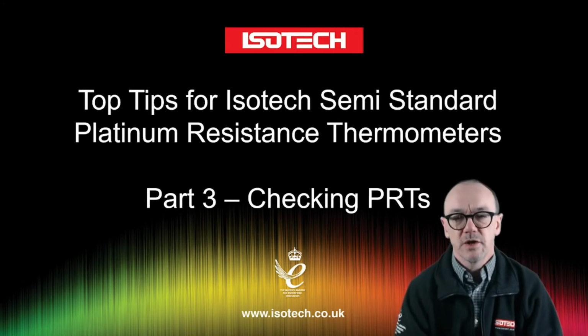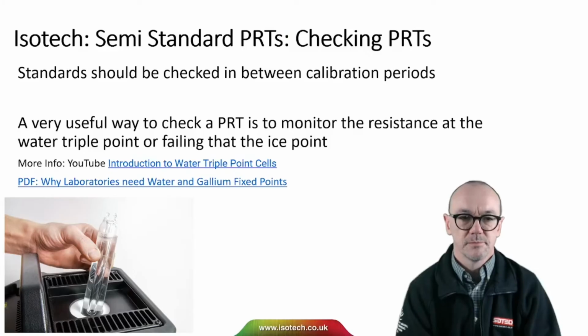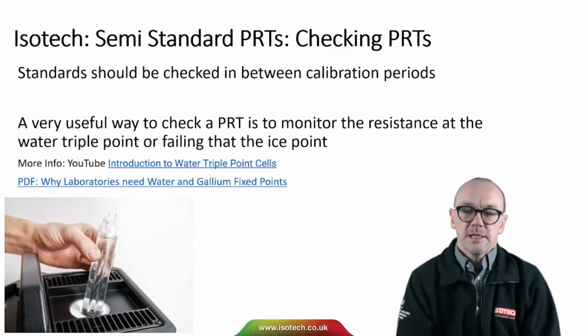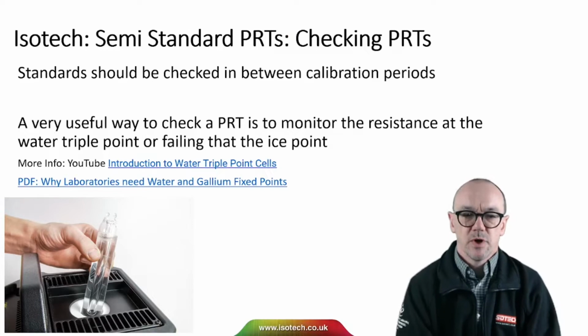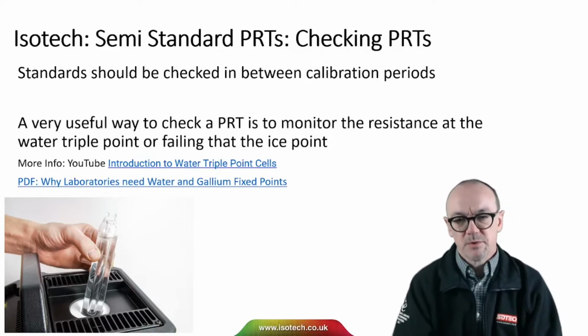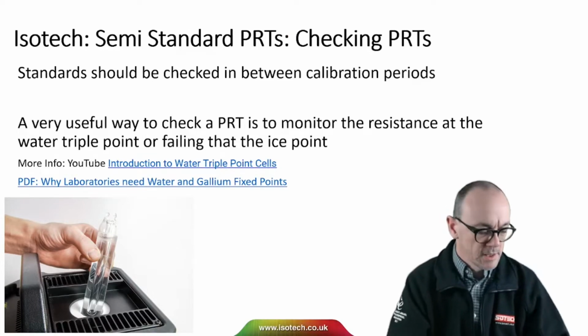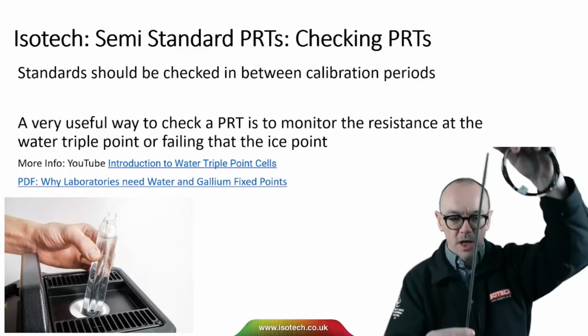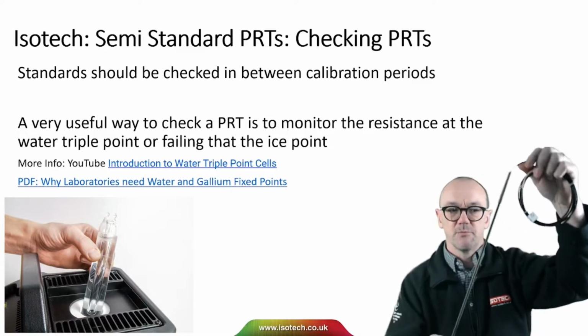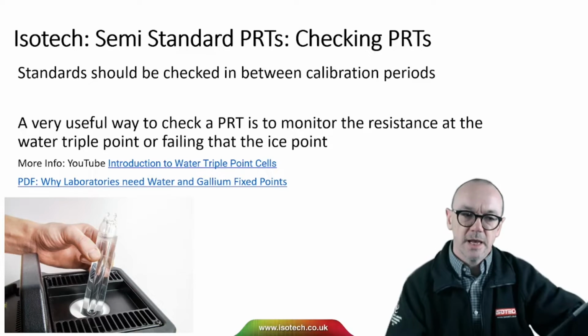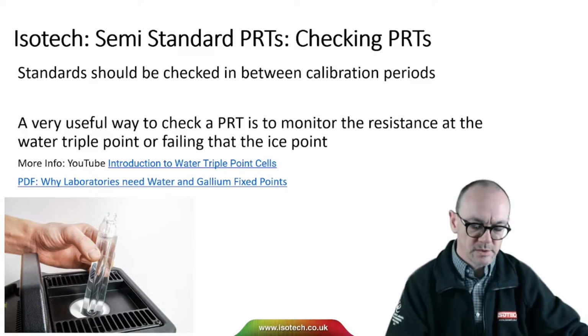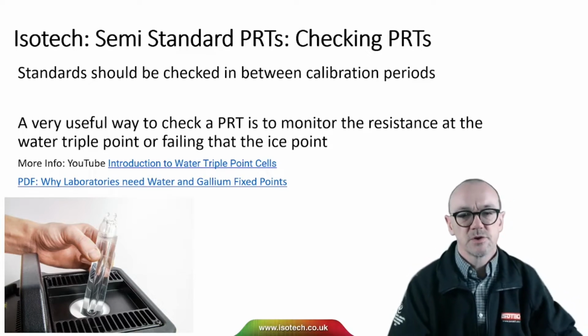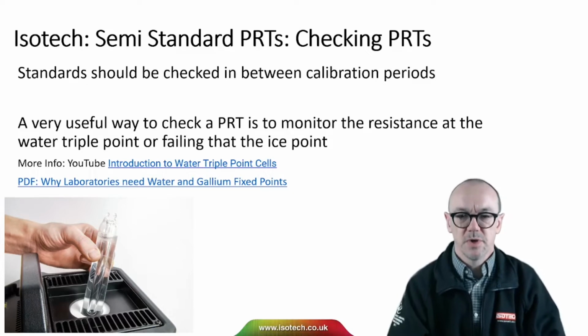And in this brief section, we're going to look briefly at how we might check and validate a PRT. So, standards should be checked in between calibration periods. If we have the thermometer calibrated maybe once a year, that's really very useful. But if the thermometer drifts in between calibrations, then we'd have a headache because we wouldn't know at which point the thermometer had drifted. So it's best to check in between calibration periods.